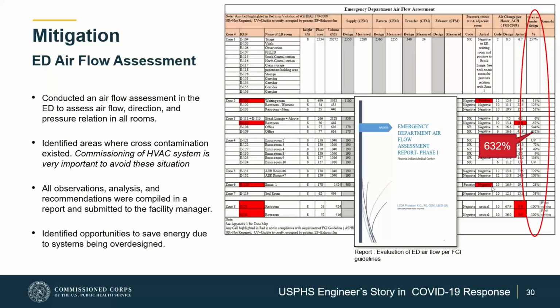To make a room negative, people always think increasing the return from a room, where people generally spend their time, is the way. Very few think about choking the supply of a room and adding more air in the hallway. This way you can change a room from positive to negative without overloading the HVAC system. If you don't change the supply and just keep increasing the exhaust in each room, because the general perception is you just have to jack up the exhaust - but from a negative or positive standpoint, the system doesn't see where the air is coming from.